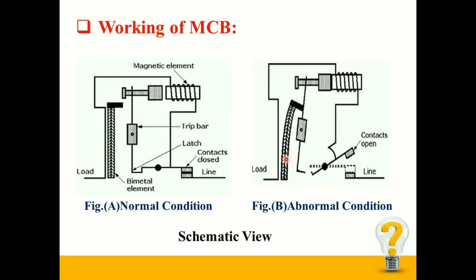As current flows through the bimetallic strip, it heats up and bends to release the mechanical latch, due to which the contacts are separated and the supply is isolated. The deflection time of the bimetallic strip is directly proportional to the amount of current flowing through the strip — the higher the current, the faster the deflection of the strip.